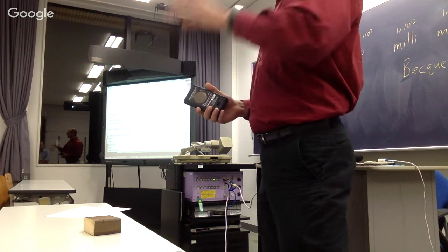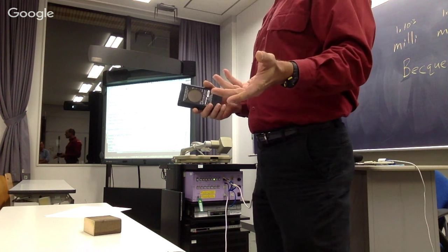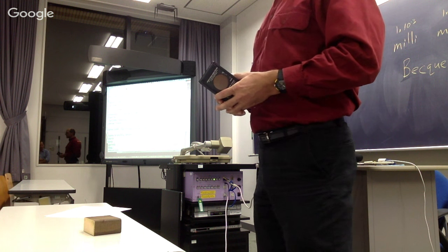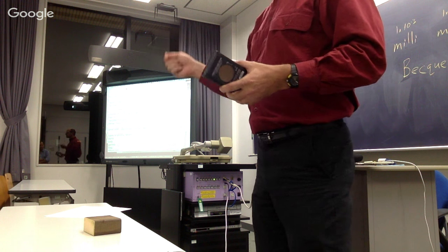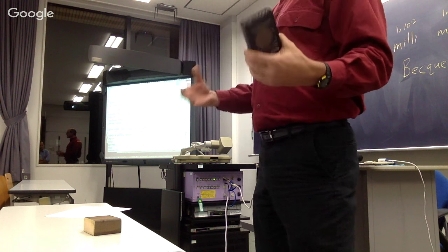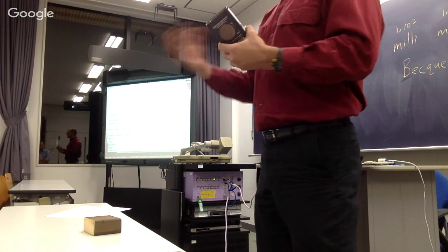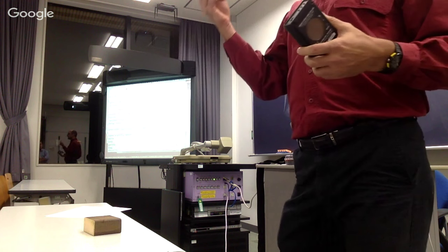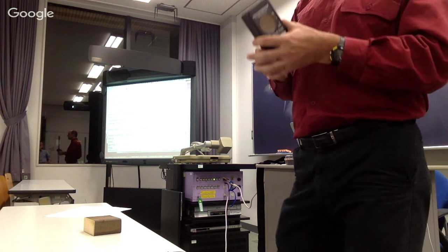But then an event happens, an ionization event, that knocks some of the extra electrons off the gas inside, and that electron knocks the electron off the next one, and it causes what we call an avalanche. So all of those extra electrons we've stacked in the gas start moving around. They move to the electrodes and conduct through the wire and make a pulse.